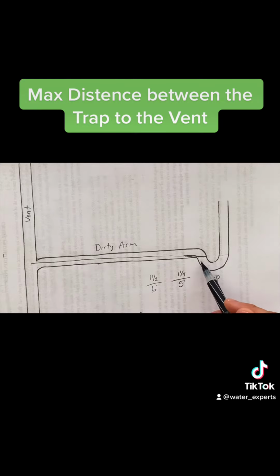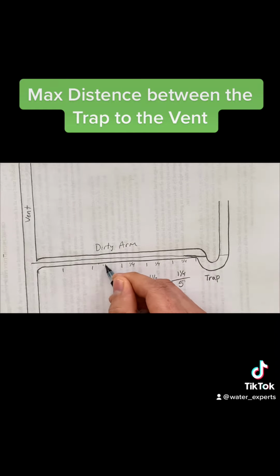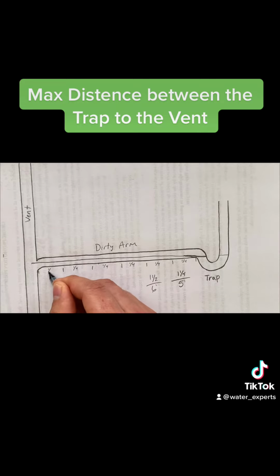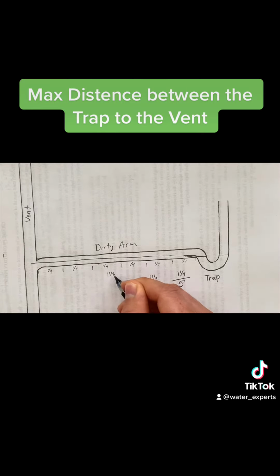So we know that sewer drains are supposed to be sloped at a 1/4 inch per foot. So let's imagine that this is a typical 1.5 inch drain for a sink, which is very typical. So let's divide it into 6 different sections. There we go. So there we have 1, 2, 3, 4, 5, 6. So if this pipe is sloping at a 1/4 inch per foot, we can say that every single foot it is dropping a 1/4 inch. And this is going to repeat itself 6 times. So if we add all of these quarters up, it is going to add up to 1.5 inches.